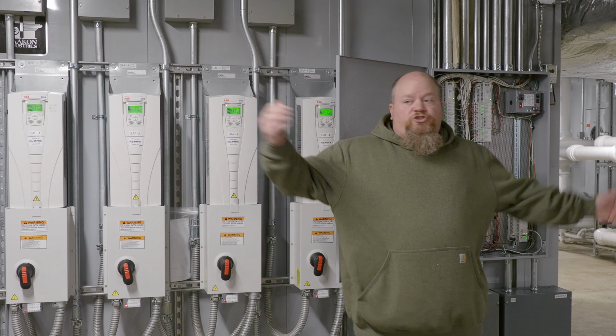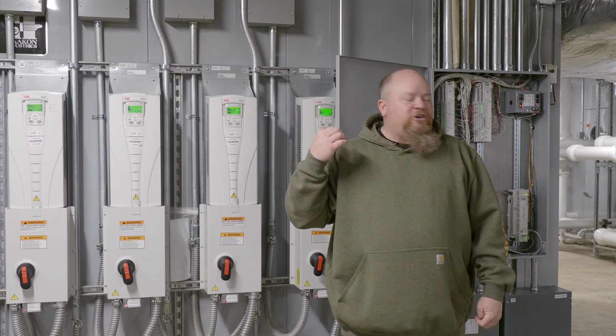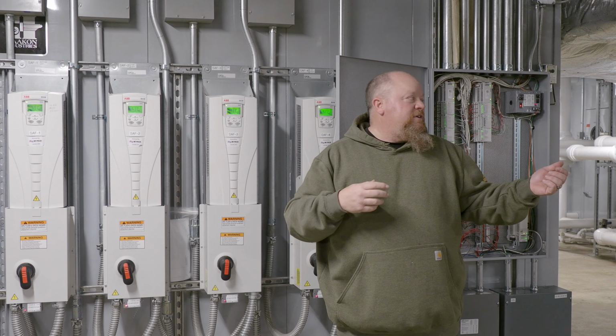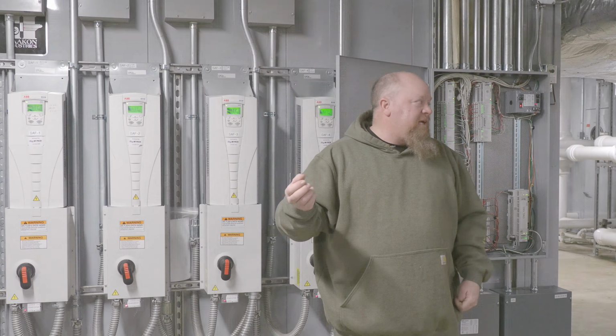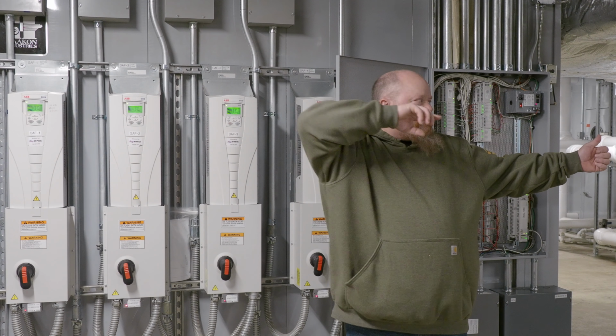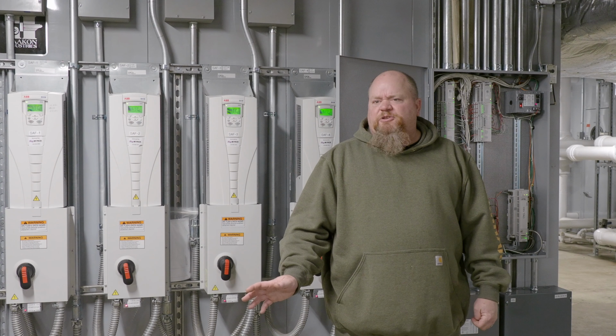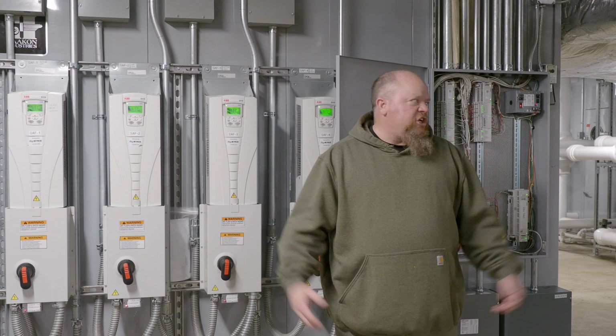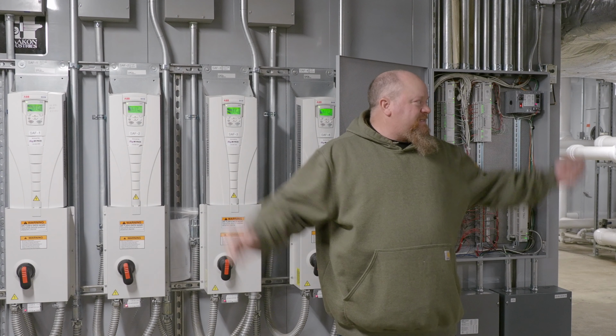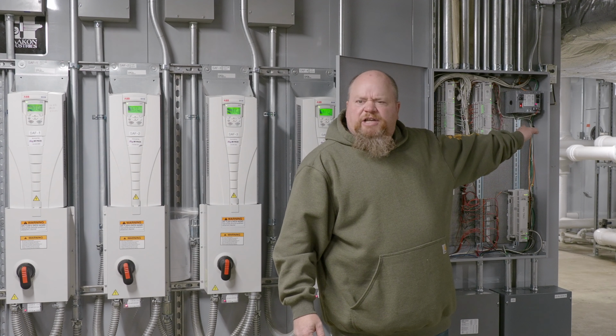Inside the air handlers, because they're so big, we have multiple sensors. Mixed air sensor, there's four temperature sensors, and we wire them 2 in series with another 2 in parallel. I have run into it before because it's just too much area to have one temperature sensor pick everything up. There's probably 4 low limits, I'm assuming. Do you remember, Jeff? It's such a big area. So if a low limit were to trip, there'd be 4 spots that could have reset buttons. They're all on the outside of the air handler.